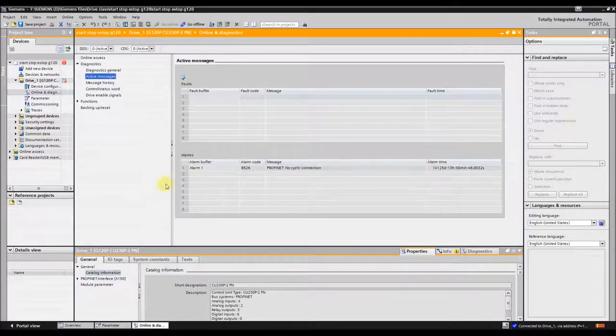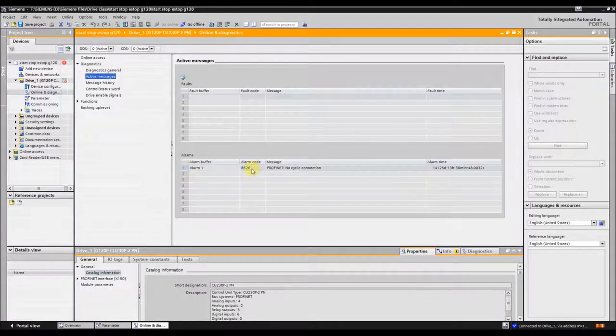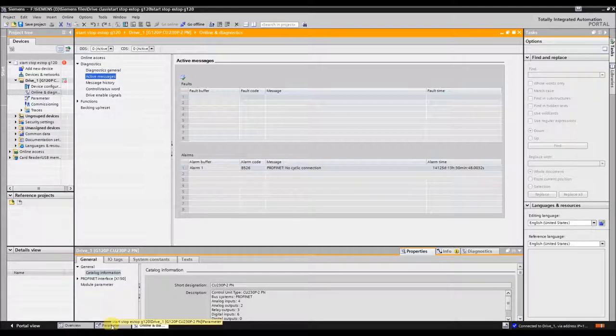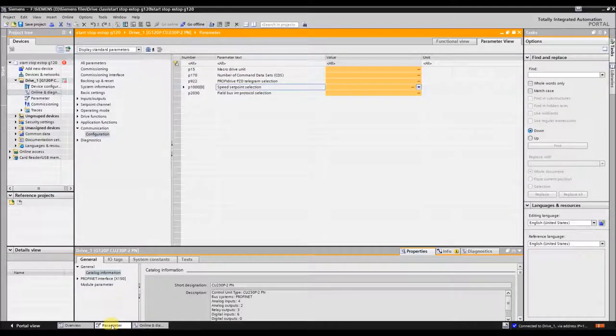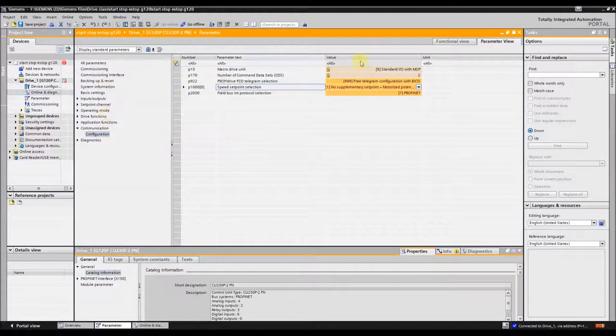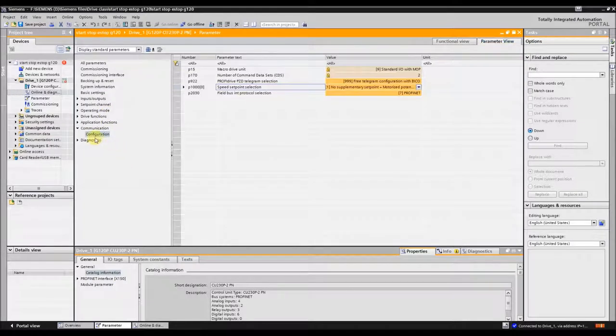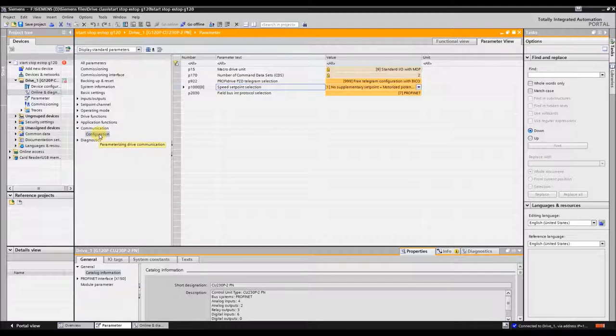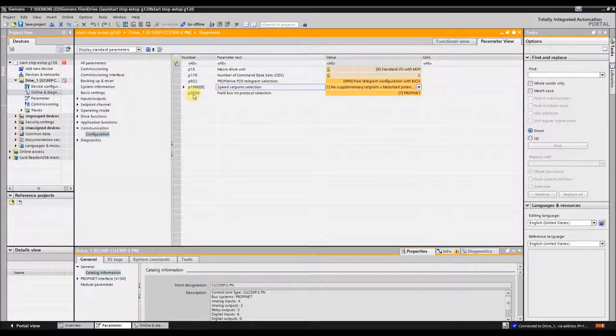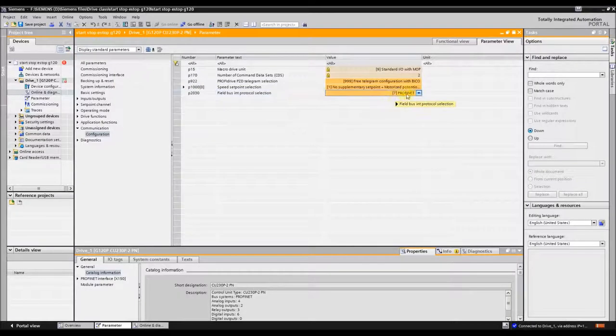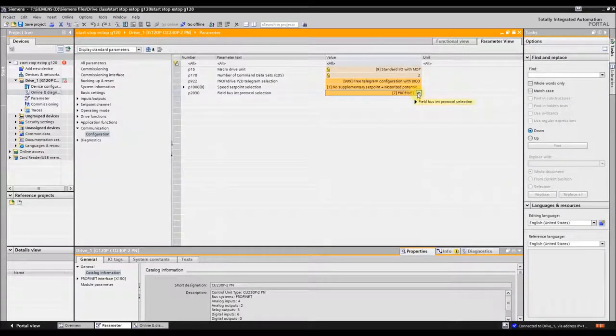The fastest way to get rid of this alarm message is to go to your parameters or on the controller, go to parameter view, then click communication. Under communication, click configurations. On parameter 2030, you need to set that to no protocol.